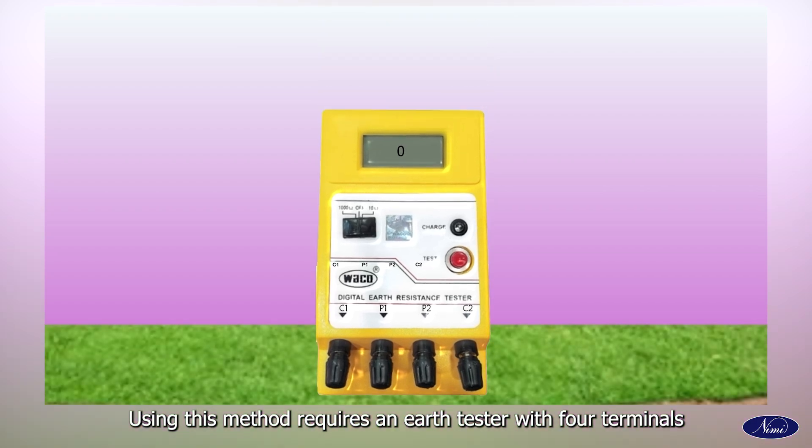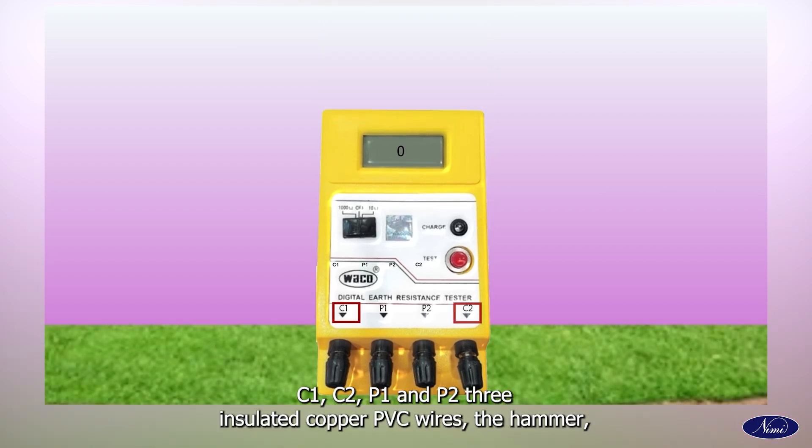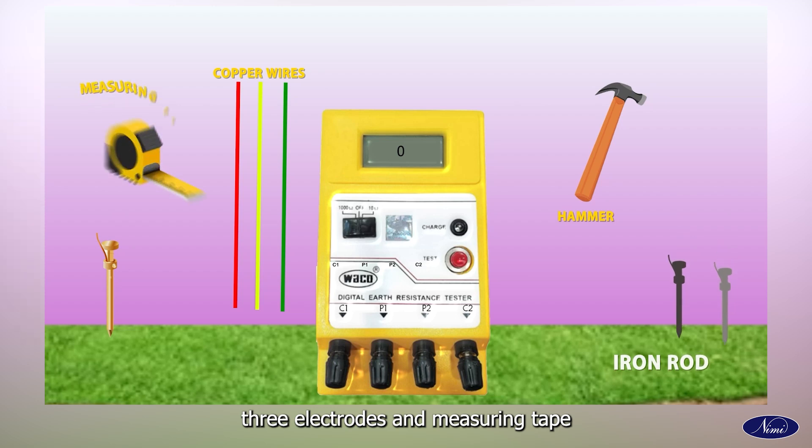To measure the earth resistance using this method requires an earth tester with four terminals: C1, C2, P1 and P2, three insulated copper PVC wires, a hammer, three electrodes and measuring tape.